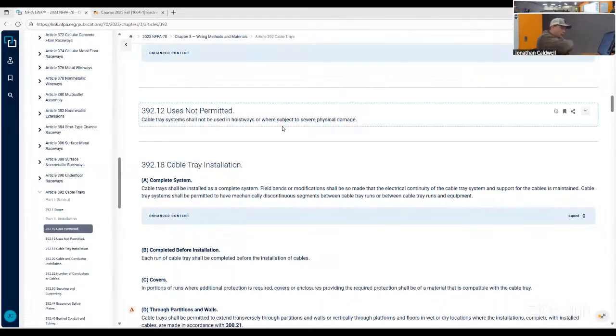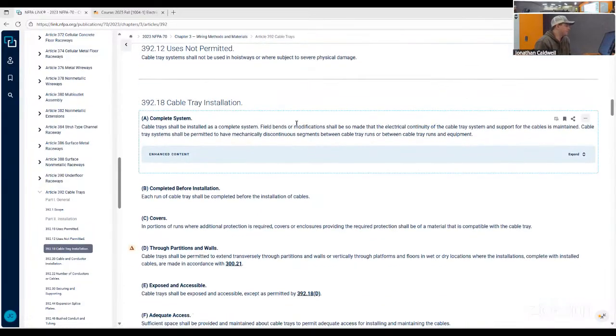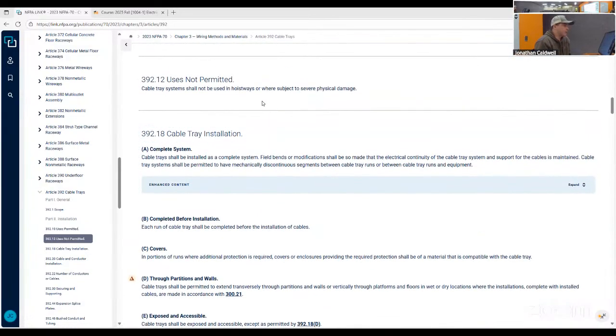Use is not permitted. Cable tray systems shall not be used in hoistways or where subject to severe physical damage. So hoistways, being below a bridge crane or, yeah, this is where things get hard because I have coworkers in here who say that's not true, because we have installed it before. But here's the problem: an industrial establishment can say, oh, only a qualified person will be servicing it, so it doesn't matter. So that's where you can throw the code book at them.